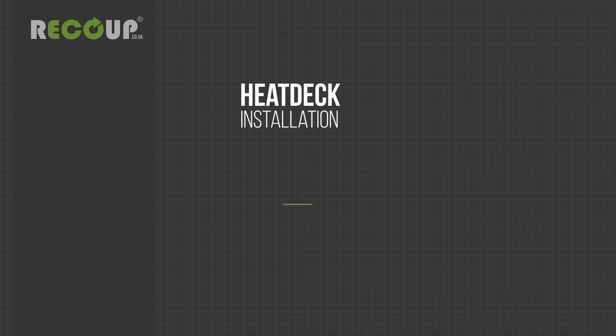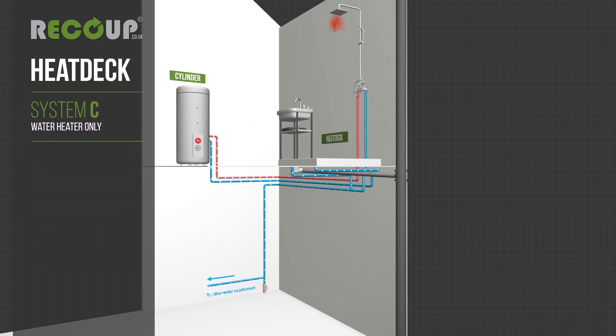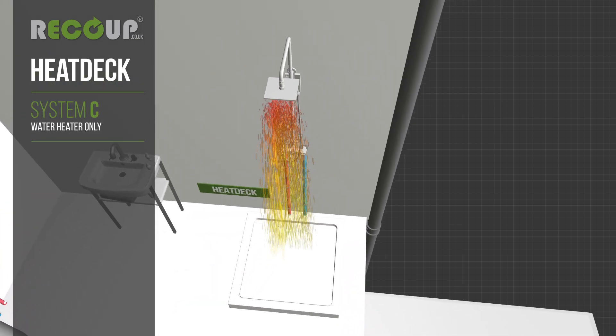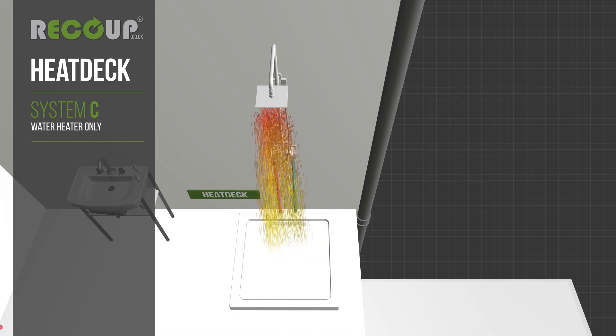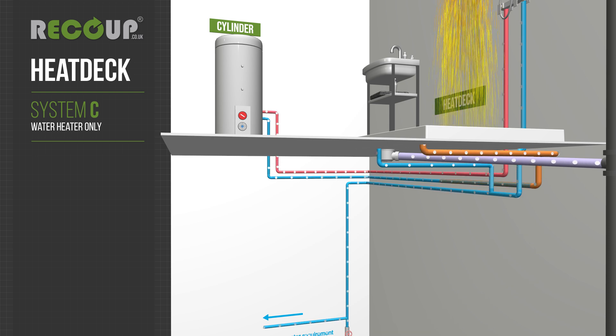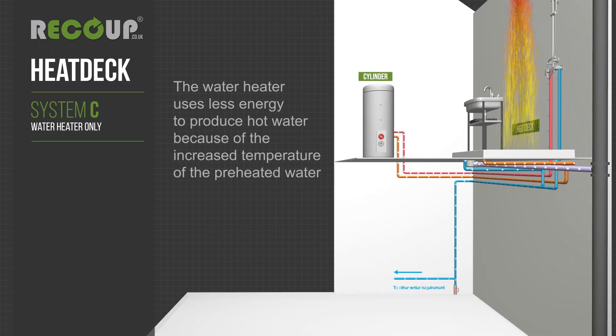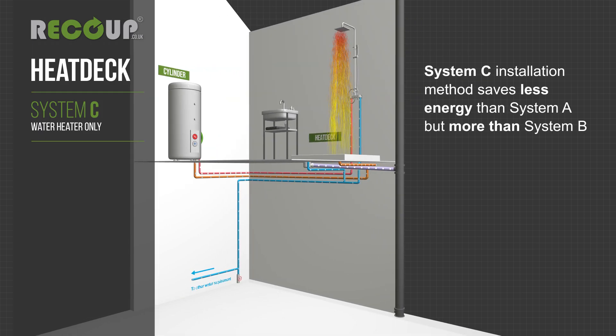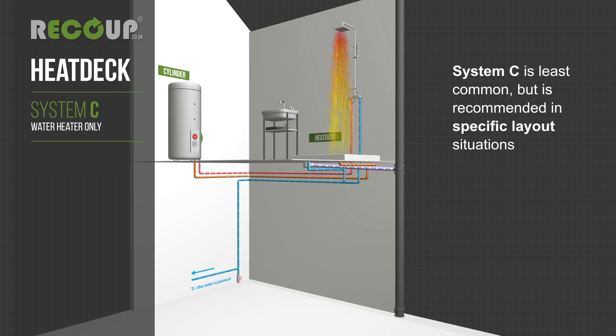System C supplies preheated water to the water heater only. As with system A and B, heat from the shower wastewater is exchanged in the Recoup Heatdeck to preheat the mains cold water. Preheated water is supplied to the water heater only. The water heater uses less energy to produce hot water because of the increased temperature of the preheated water. System C installation method saves less energy than system A but more than system B. System C is least common but is recommended in specific layout situations.